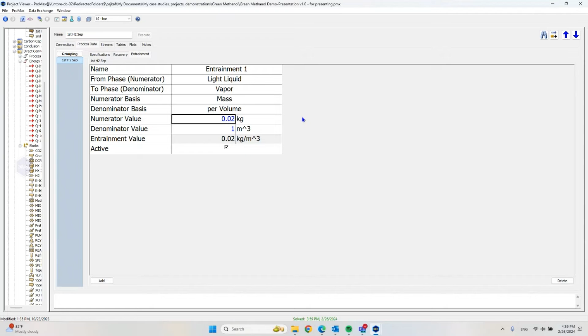To get rid of the KOH or KOH solution from the vapor, there are several strategies. One of them could be using a column, feeding the fresh water from the top and scrubbing the KOH back into the system. The other way could be using an air cooler to knock out the water, and then a separator to separate the mixture. Of course, due to the crossover of oxygen, part of the oxygen will end up on the hydrogen side. For that reason, we can use a deoxo unit. This is just a normal Gibbs minimization reactor that will convert hydrogen together with oxygen to water.